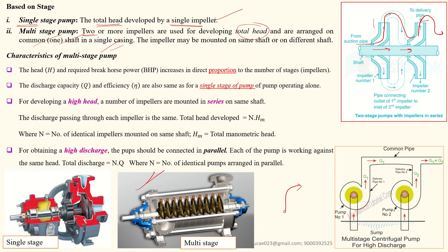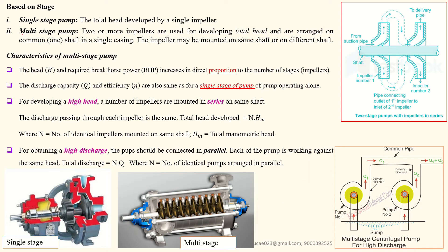For example, if a pump has 10 impellers and each impeller develops a head of 10 meters, the total head is 10 × 10 = 100 meters. If each impeller practically delivers 6 meters, the total head is 10 × 6 = 60 meters. Such calculation questions may be asked in exams. This is the multi-stage pump concept.